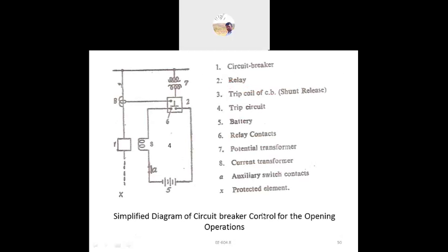You can see it simplified here: this is the line, and we have the circuit breaker, the CT and the relay contacts. You can see this is the PT. How will it work? First we have the circuit breaker, second the relay contacts, third the trip circuit and contacts, and fourth the battery, which supplies the relay. The current transformer, the CT, gives the current signal, and here we place the potential transformer, which gives the signal to the potential coil. In the relay we have two coils, one is the current coil and the other is the voltage coil. From the current coil we get the signal from the CT, and the secondary of the potential transformer is connected to the potential coil.